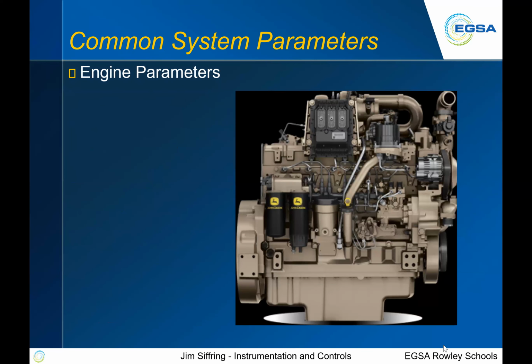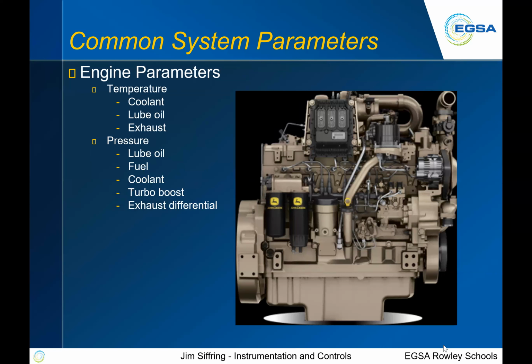So what are the parameters we look at? If we just take the engine itself, what are the parameters on an engine? This is certainly not inclusive of everything, but many of the things we want to keep our eye on. So engine temperature, of the coolant, of the lube oil, of the exhaust system. We want to look at pressures, probably lube oil pressure, fuel pressure, coolant pressure possibly, turbo boost pressure, exhaust differential pressures, things such as that. Levels: how full is the tank? How much does this thing have in it? We want to look at coolant levels, lube oil levels, fuel and DEF. If you've had to work with any of the new DEF systems, they won't run without DEF.